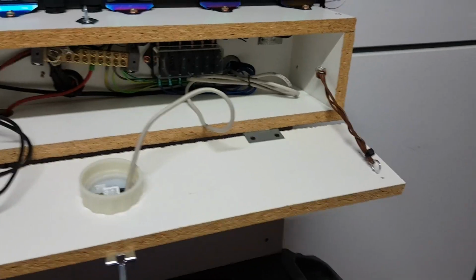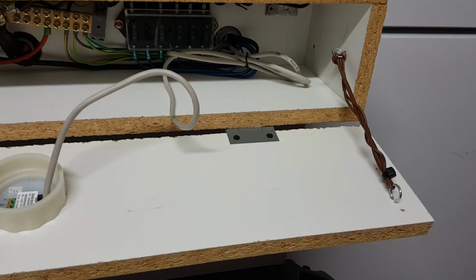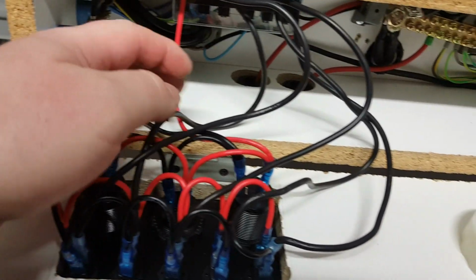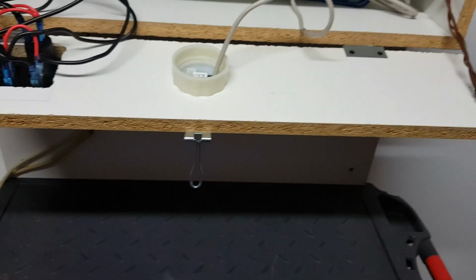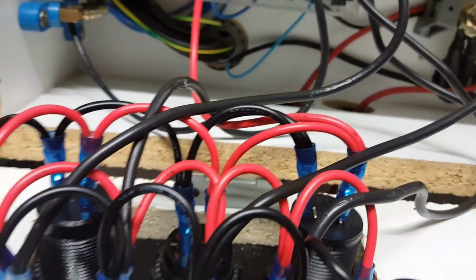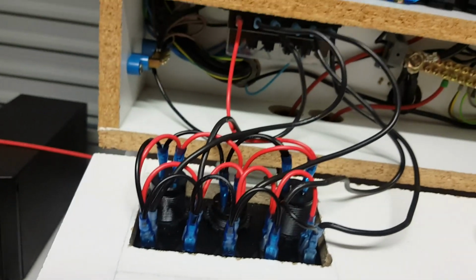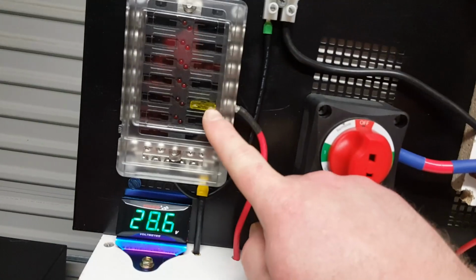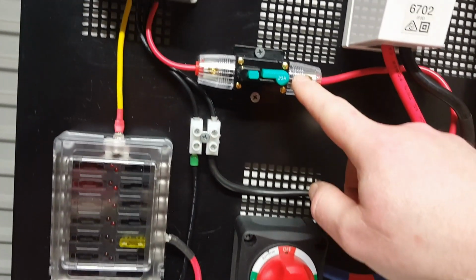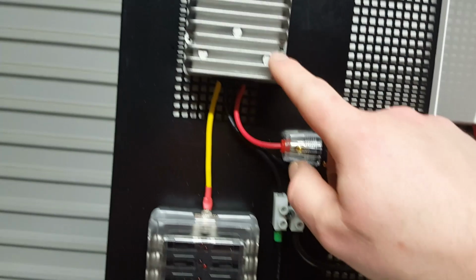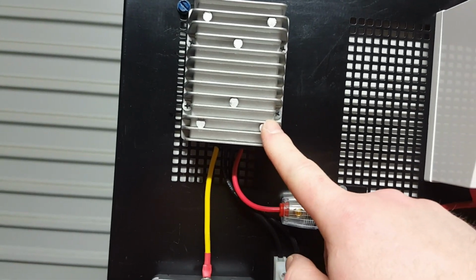I have that little wire holding it down, so these cables don't get any tension on them and don't get pulled out if it opens too far out. But it's all pretty much wired up. Each of these fuse boxes contain 1 amp fuses, except for the very first one, which runs this panel - that one's a 20 amp, same as that one there, 20 amp, as well as that circuit breaker, 20 amp, although the step down converter is a 30 amp max, so we shouldn't need to use all that much power.